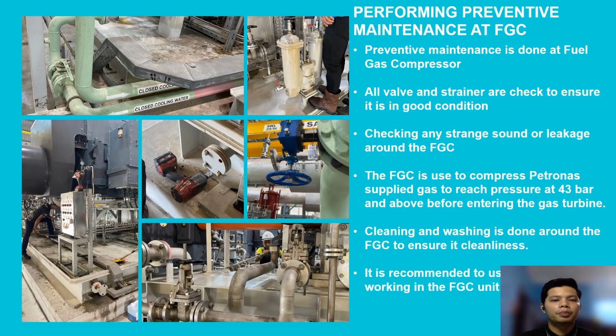Then we do the preventive maintenance at fuel gas compressor (FGC). FGC is used to compress supplied Petronas natural gas to above 43 bar. It is requirement for the 9HA gas turbine to function efficiently. The preventive maintenance is done by checking any leakage from pipe, valve, strainer or strange sounds produced around the 2 unit of the FGC. Then we clean the floor of the FGC to ensure it is in safe and clean condition.